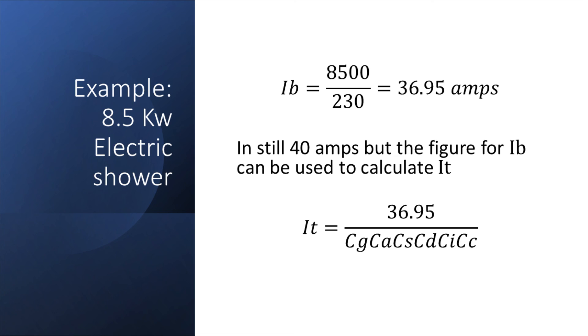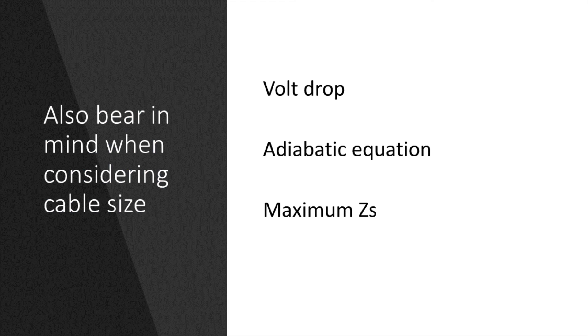Now you may be thinking, what if another electrician comes along later on and replaces the shower or the electric heater for a larger one that exceeds the rating of the cable? This may be a potential downside of this method that may mean in practice you still prefer to size the cable to be greater than the rating of the protective device. Also, when selecting the cable size, we need to consider the voltage drop, the adiabatic equation, and compliance with the maximum ZS. So there are other factors that affect the sizing of the cable as well.